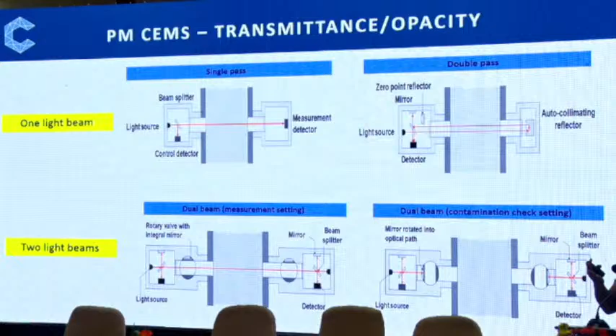An opacity meter is suitable for medium to high concentration. If you have 20 milligram and so on, I would suggest that's not the right equipment. Normally we have a higher dust concentration, so for 50, above 100, it is perfectly fine. If you get lower than that, it is better to go to backscatter. If you are pretty low, you have to go to forward scatter.